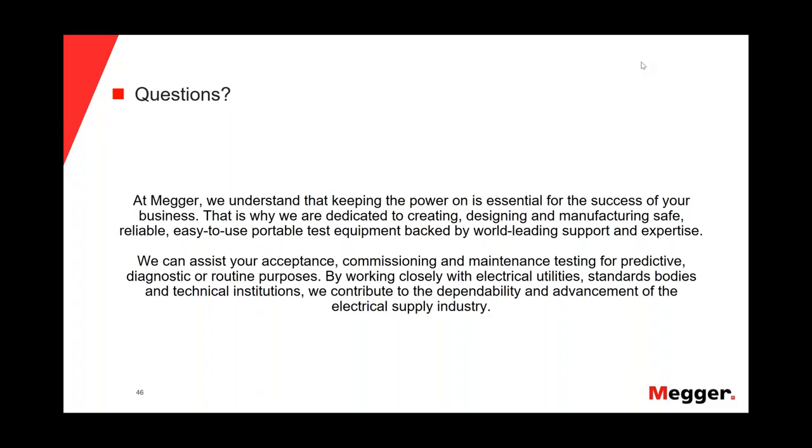Well, it depends how the cable was stored. For instance, if it was under the shadow, the temperature conditions, etc. But I would say that maybe the first test I will do is to test the jacket of the cable, and then I will do a commissioning VLF test. I will not be concerned about water trees in the cable, because for water trees we need water inside of the cable and electrical stress. So I will not be concerned about the water trees, but maybe the jacket.